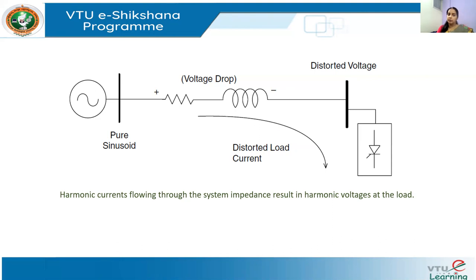The voltage distortion at the load side is a result of distorted current. The supply voltage is a pure sine wave, the transmission system is linear, but the load side has a non-linear circuit. Because of the non-linear load, there is a distorted load current. This distorted current passing through the linear series impedance causes a voltage drop for each harmonic component, resulting in voltage harmonics appearing at the load bus.